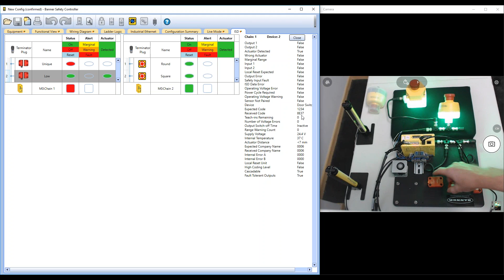Where you could use something like that is if you had machines with multiple tool inserts for the same machine—you could tie the RFID tag reading portion, which is a non-safe thing, but from a process standpoint you want to know what tool is there before you run. You could tie the RFID tag value to tool 1, this one to tool 2, and know from a process standpoint if you have the right tool in place. You could then tie that into the safety doors on the same chain to also check all doors are closed. So: tool in place, OSSDs are on, it tells the PLC what tool it is based on the RFID tag, the door is closed from a safety perspective, OSSDs are on, and the machine can run as long as the PLC confirms it sees the right tool. You could tie that same RFID tag into an E-stop string as well, however you want to do it, but it's a really neat feature because we're sending sensor-level information, like the RFID tag value, up to the PLC.